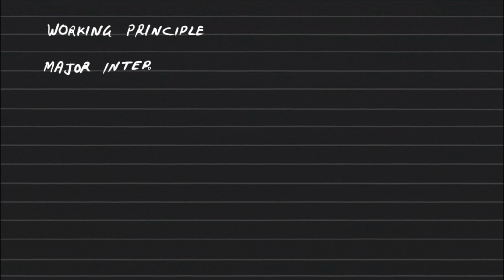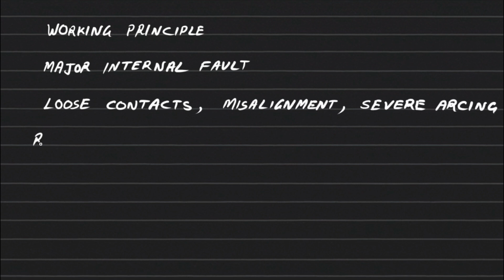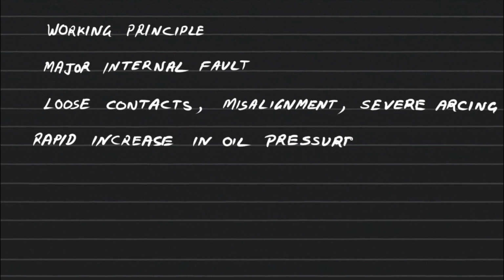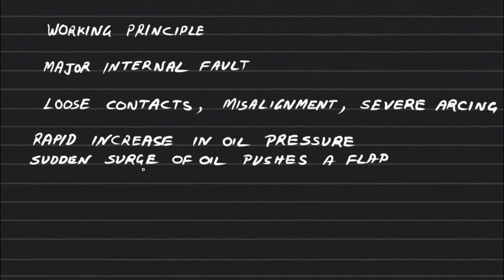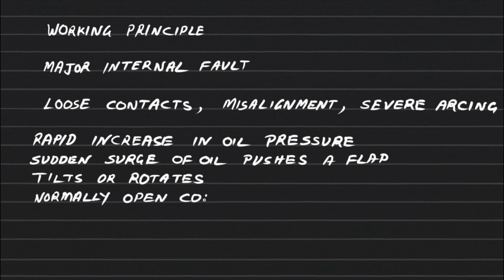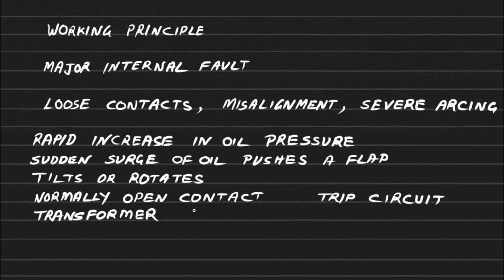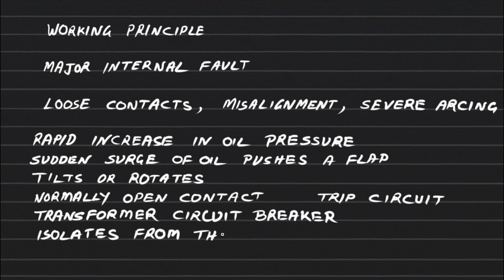If a major internal fault occurs inside the diverter tank due to loose contacts, misalignment, or severe arcing, it produces a rapid increase in oil pressure. The diverter tank is much smaller than the main tank, so even a small amount of arcing causes a sudden surge of oil. This high-velocity oil flow passes through the OSR, and as it enters, it pushes a flap or vane fitted inside the relay. When the oil pressure exceeds a preset limit, the flap tilts or rotates, closing the normally open contact inside the OSR. As soon as this happens, the trip circuit of the transformer circuit breaker is activated, and the transformer is isolated from the system immediately.